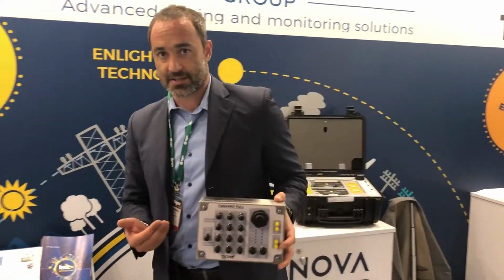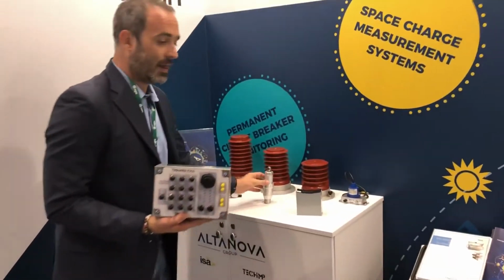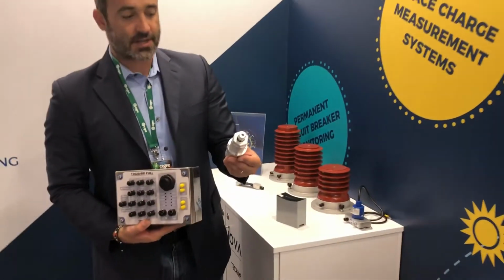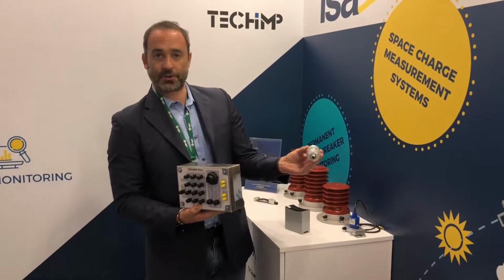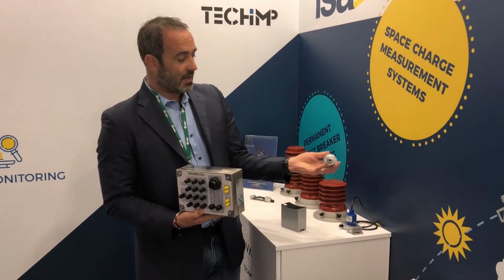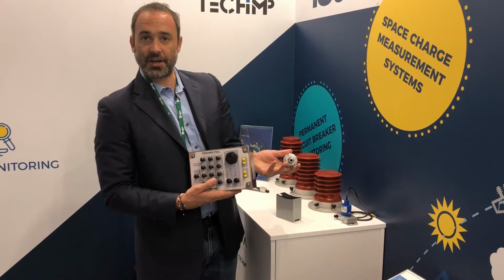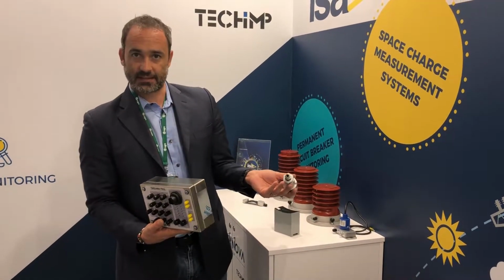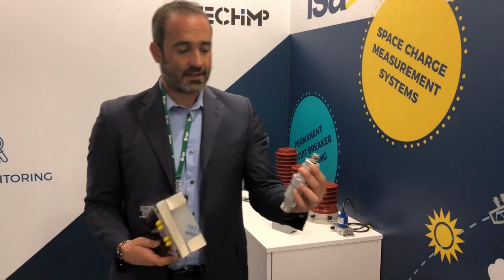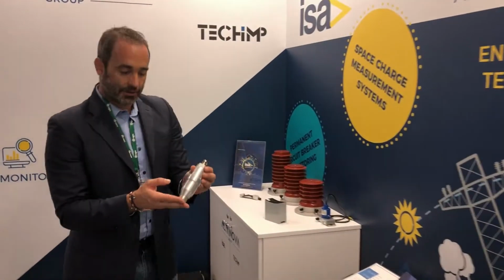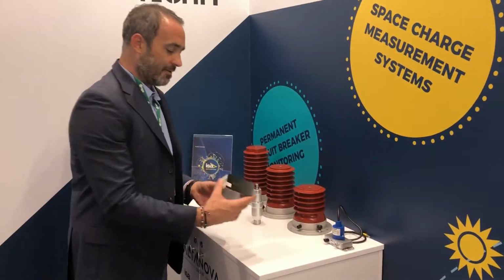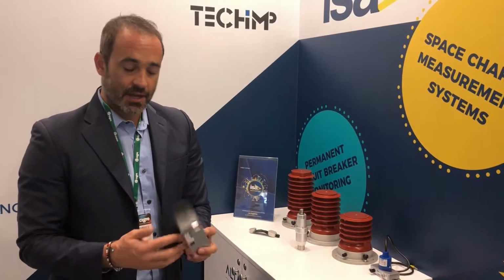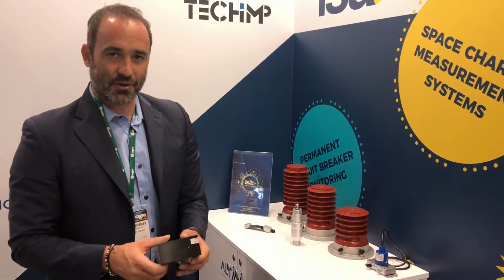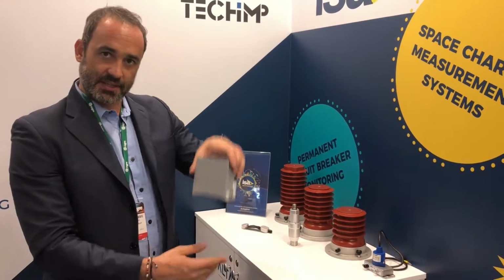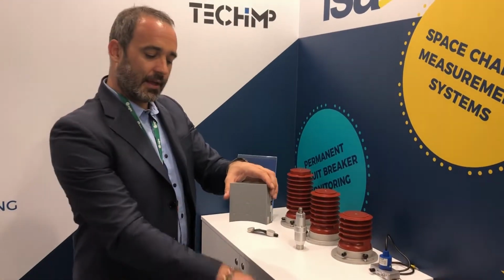Now, in order to use that device, you will need a sensor for a transformer, and this is one example of a transformer sensor. This is kind of a tap adapter, and you put this at the bottom of your bushing, and then you take a signal from here, you pass it to here, and then you measure PD and also tan delta. So this would be, as we said, the sensor for the transformer. And I'm going to show you a few more sensors. Apart from the transformer sensor, we have a GIS antenna up to 3 GHz, which is used, as the word says, for GIS. You can see the special form because this needs to be put on the spacer between the two segments of GIS.